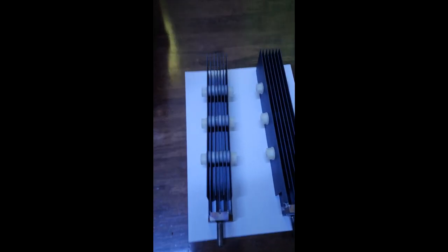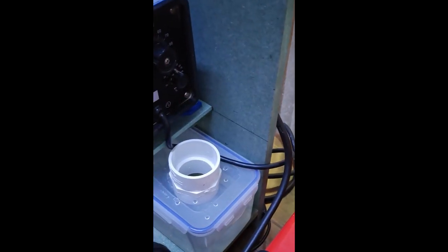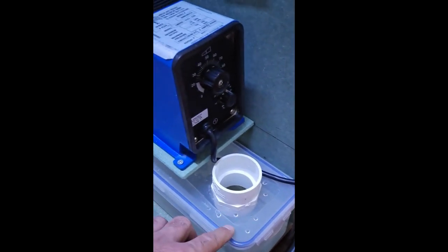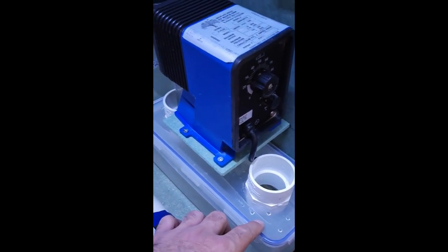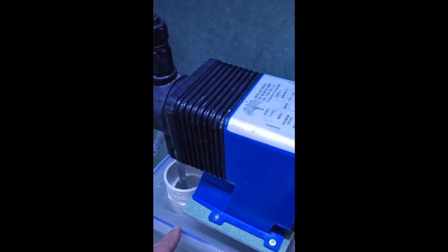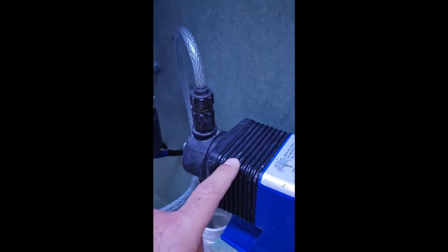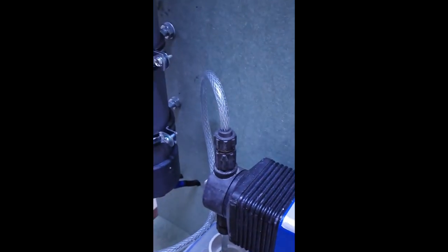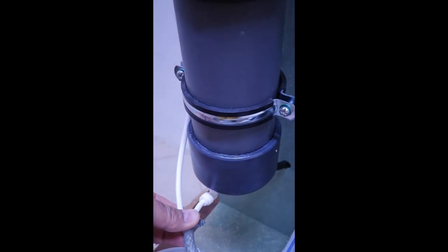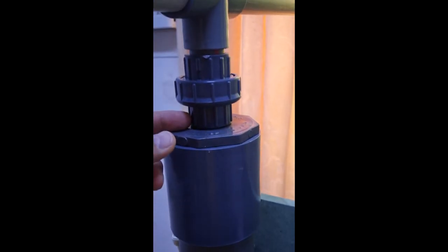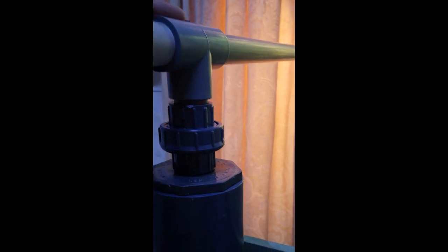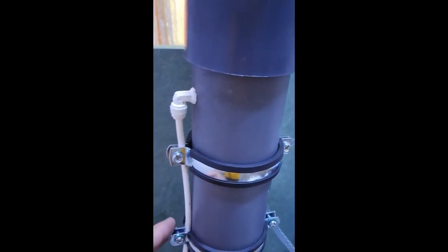We have one piece of the cathode and anode assembly. This is the sodium chloride solution tank, and the solution is pumped by a dosing pump which is only 100 GPD and it doses directly inside to the electrolyzer chamber. Then the product comes out: we have the hydrogen gas which is exhausted through the exhaust pipe, and the resulting sodium hypochlorite solution is pumped to the collection chamber.